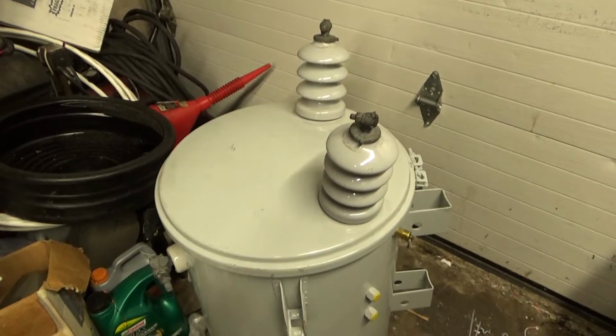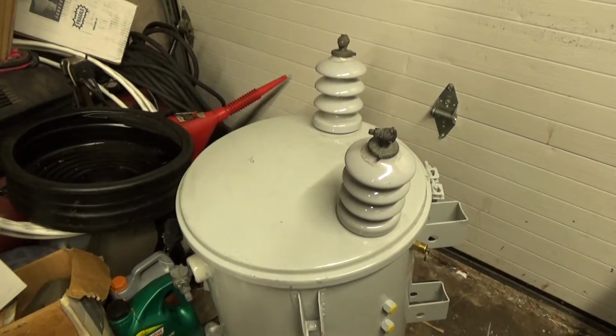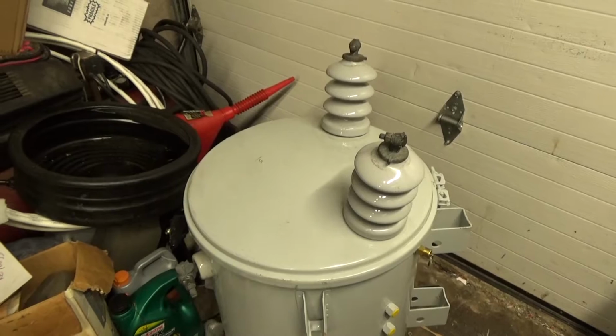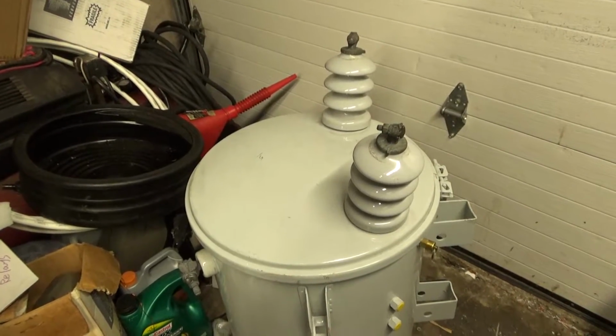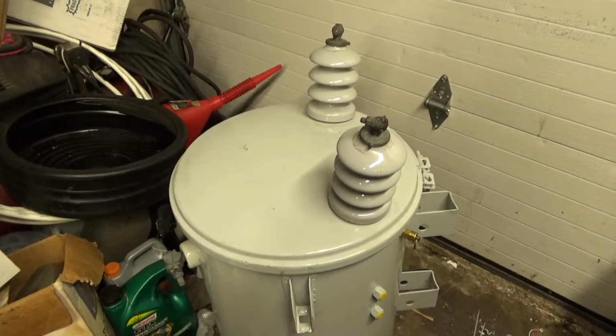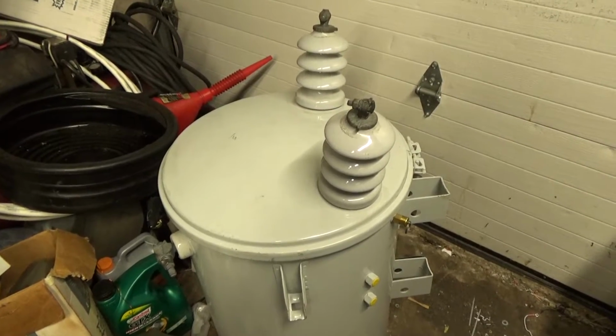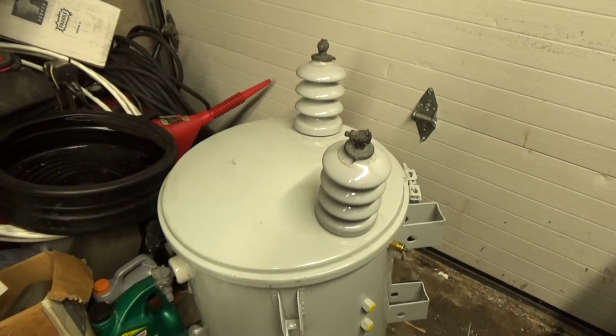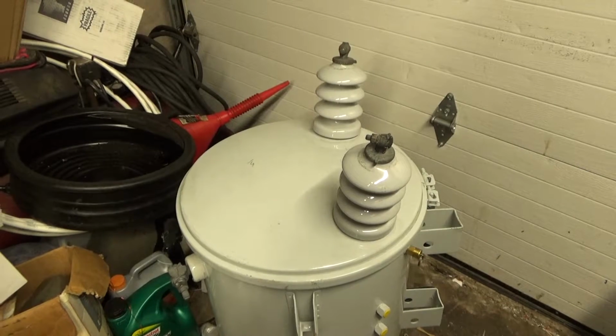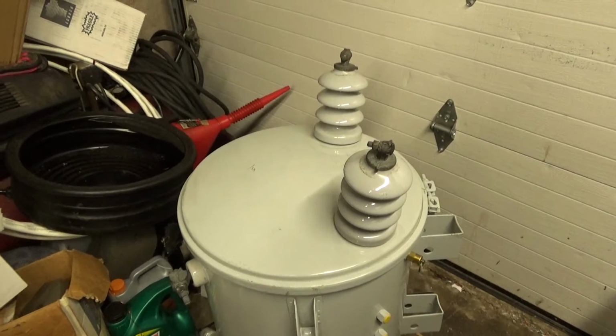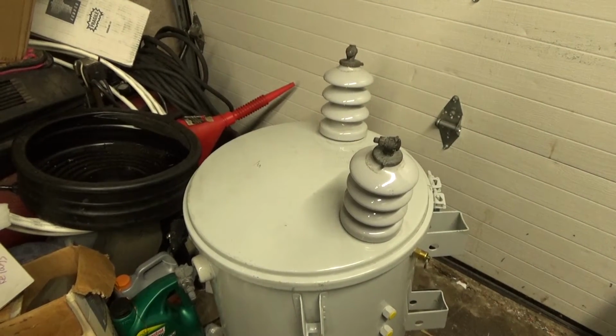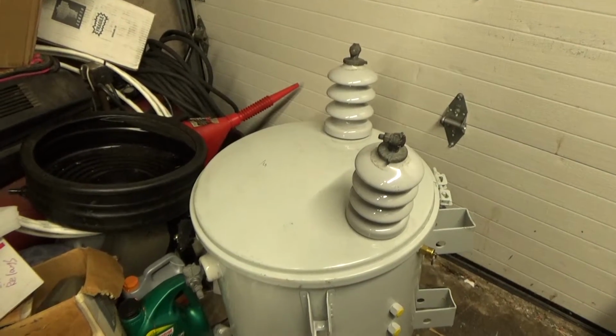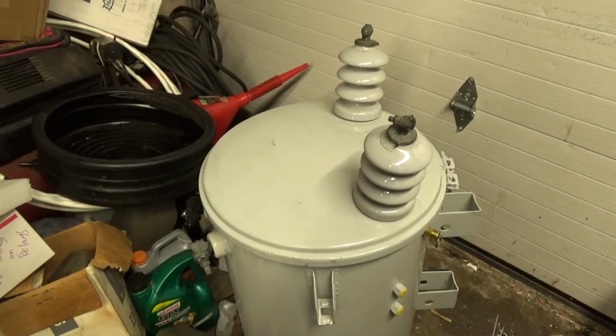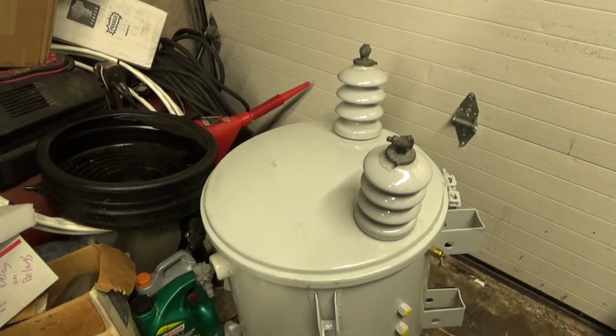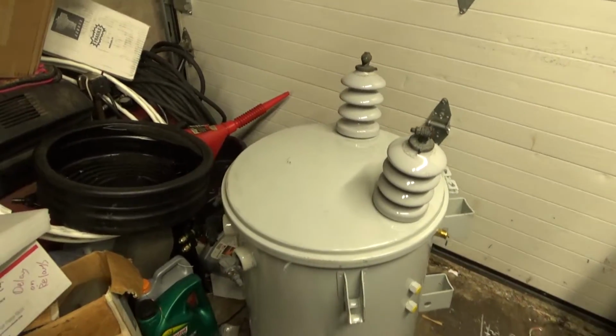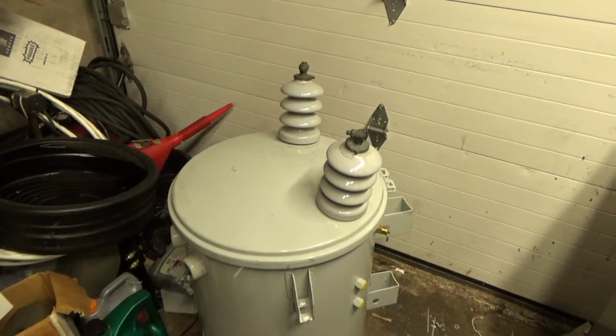These transformers are designed to run most efficient at lower loads versus higher loads, because a lot of times they're sitting on the street, and when people are at work there's very little to no load on them. If they're inefficient at low load, then the power company would lose a lot of power, a lot of money in the process.